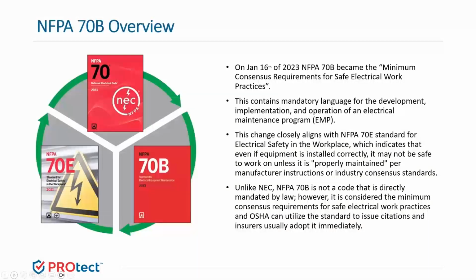The latest edition of NFPA 70B, which is a standard for electrical equipment maintenance, became effective in January of this year. This is noteworthy because for the first time, this became a mandatory standard instead of a non-mandatory recommended practice. This now puts NFPA 70B on par with NFPA 70E, which is the standard for electrical safety in the workplace. Together, these two standards require employers to formally manage electrical safety and electrical maintenance risks. NFPA 70B is not a code that's directly mandated by law. However, it is considered the minimum consensus standard for safe electrical work practices, and OSHA can now utilize this standard to issue citations moving forward.